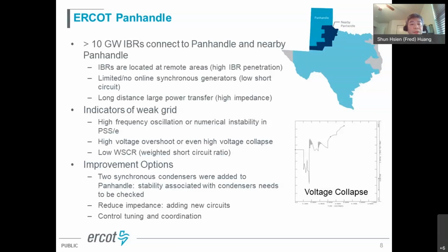So how did we identify this as a potential weak grid area? First, most likely we observe it in PSCAD simulation - when you start seeing high frequency oscillations or numerical issues, that's generally a hint the area can be weak. Or if we apply a fault, you start to see voltage overshoot right after the fault begins to increase.